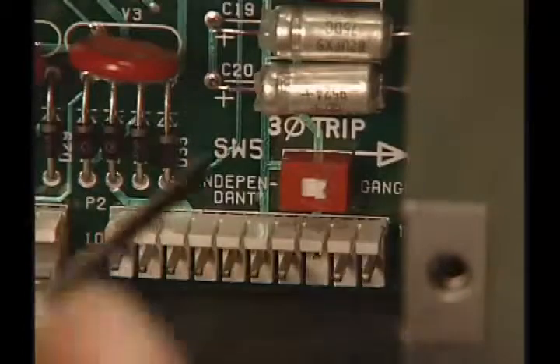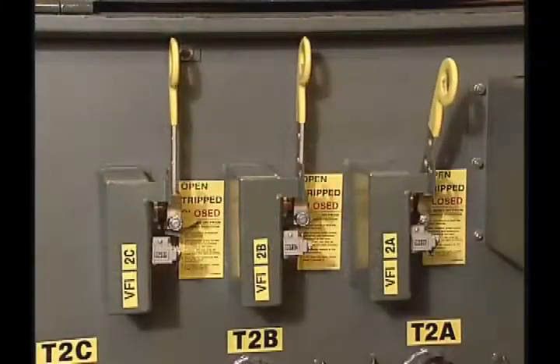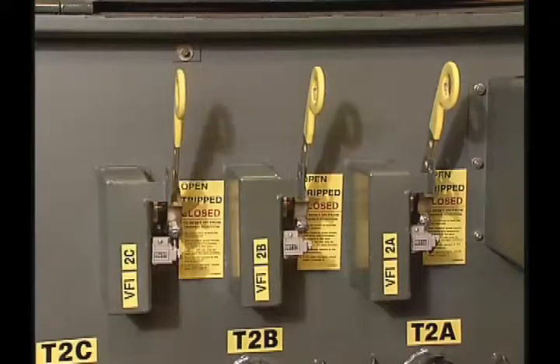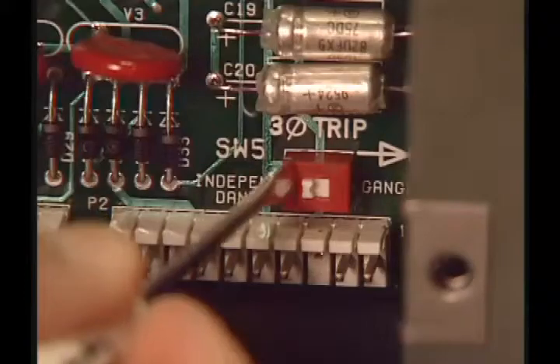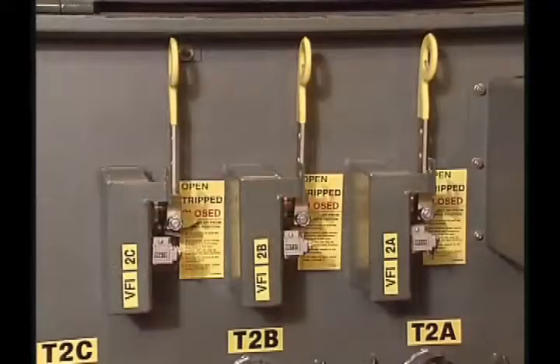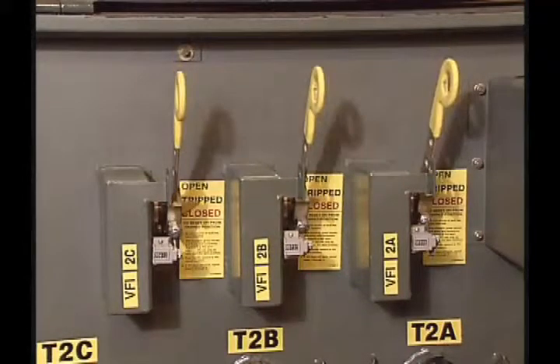The tri-phase control has a switch, allowing for either single-phase independent or gang three-phase tripping. For units with three single-phase trip handles, the control can be set for independent operation of each phase. When set for ganged operation, a fault detected on any phase causes the simultaneous interruption of all three phases.